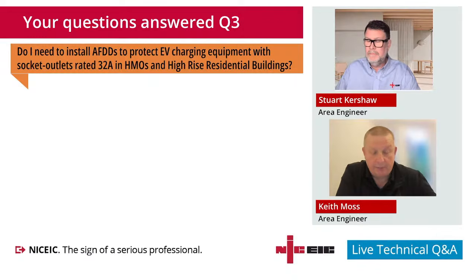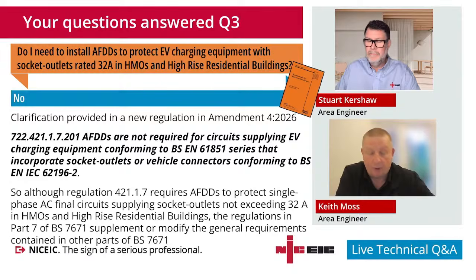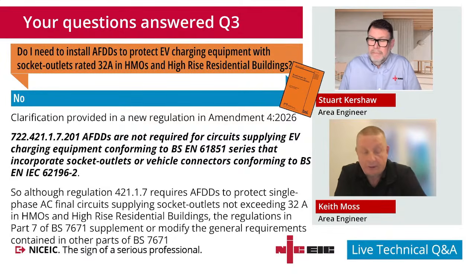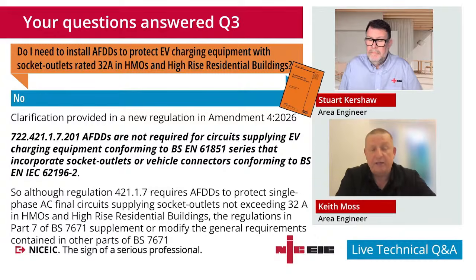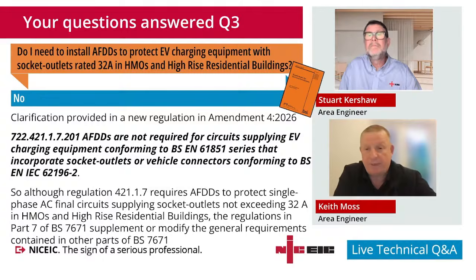No, you don't, Sam. The clarification has been provided in Amendment 4. There's a regulation in Section 722, which is the EV charging regulations. It says 722.421.1.7.201: AFDDs are not required for circuits supplying EV charging points under those requirements in a High Rise Residential Buildings. So it sort of contradicts itself a little bit with 421.1.7 where AFDDs are required, but Part 7 of BS 7671 does supplement or modify the general requirements contained in other parts of BS 7671. So it doesn't need it, no.